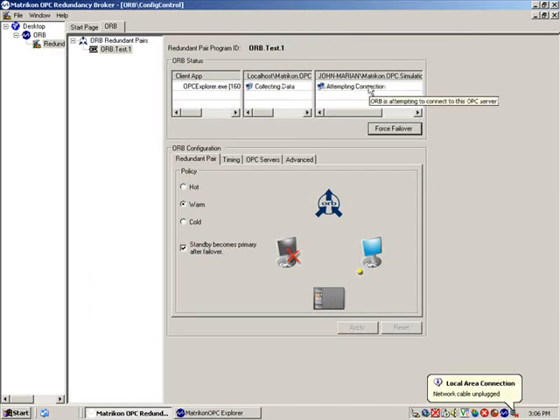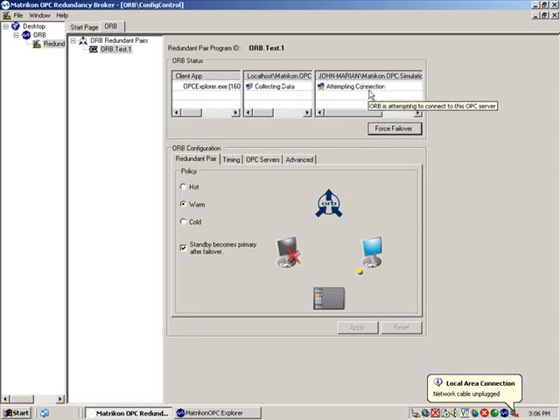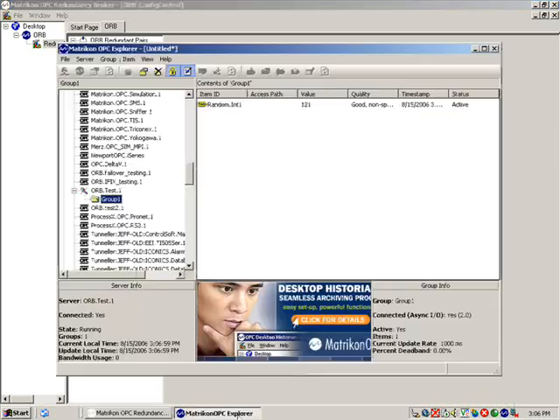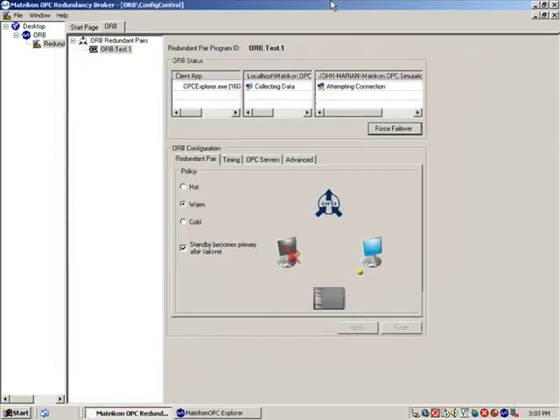You will notice that when the cable is disconnected, ORB will detect that the connection is lost to the backup server and fail to the primary server. The primary server is now collecting data and, as you can see in Explorer, is still updating values.